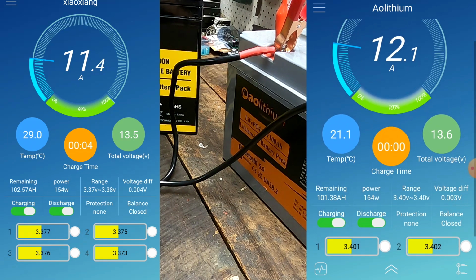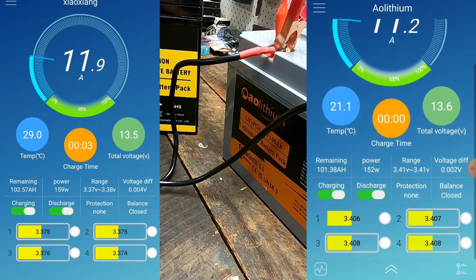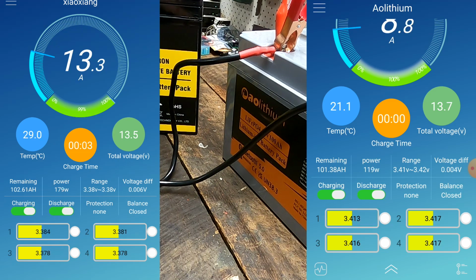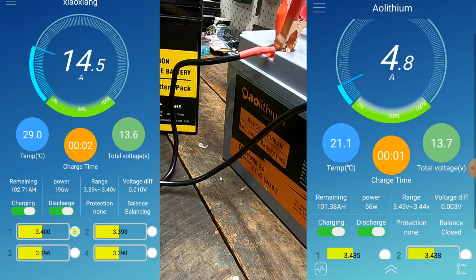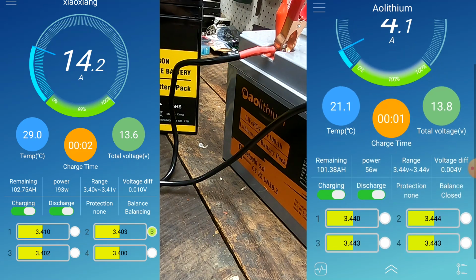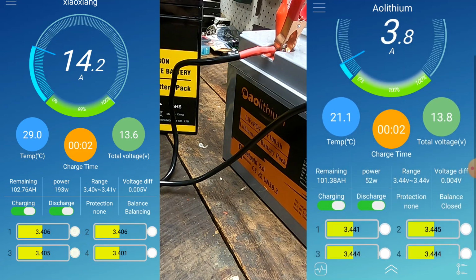So we now can see 12 amps in the AOLithium and 11 amps going into the Basin battery. As always, when you parallel batteries, they should balance each other out, so they have the same voltage of course. Here we can see the AOLithium is already charged a bit more, so it takes less power than the Basin battery, 4 amps to 14 amps. It's a good demonstration of what happens if you parallel batteries with different state of charge.